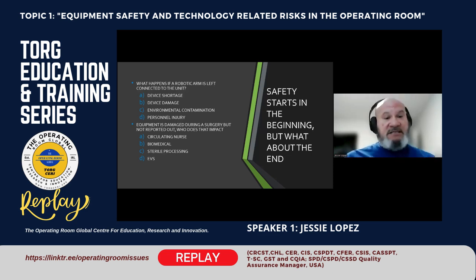If sterile processing is in charge and EVS is in charge of cleaning that unit, they might further damage it because they don't know where the damage is, and cause some type of water invasion or chemical invasion. There might be microorganisms that seep into that damaged area, and again, now you're causing a cross-contamination issue. Typically, EVS isn't fully in PPE when they go in to clean. They may have on a mask and maybe some gloves, but they don't have on the gowns and the face shield. So while they're moving things around, something may spray out and cause an injury or an exposure to one of those employees.